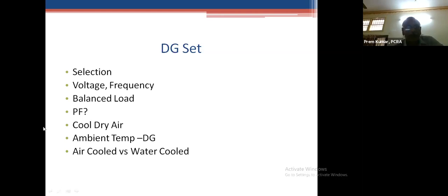Then cool dry air, ambient temperature is very important for DG as well as compressor. In summer you can see the overloading. Air cooled versus water cooled. We have found that air cooled are equally efficient, though we slightly spend more on the efficiency. Water cooled present maintenance issues and results in wastage of water. Because personally I feel water saving is more important than energy saving.